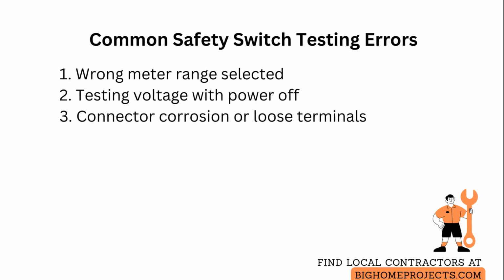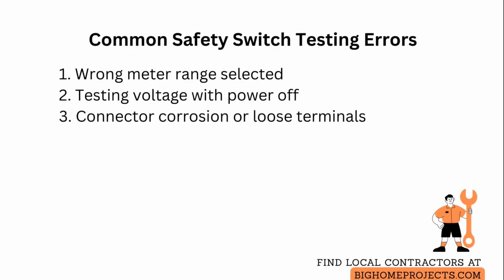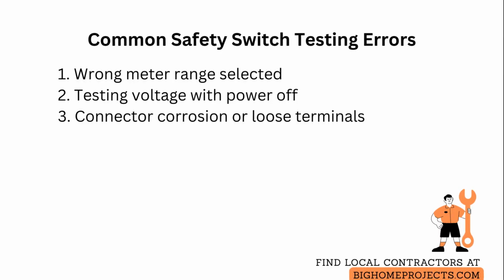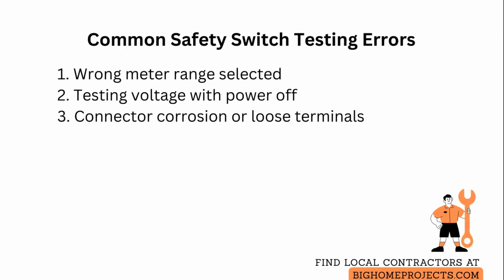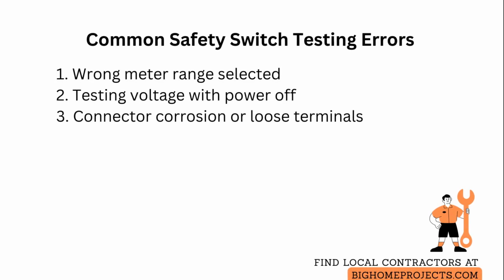Another issue is testing with power removed. When you actually need to verify the presence of control voltage, shut power off only when checking continuity or resistance. Otherwise, measure voltage live, using insulated probes and proper precautions.